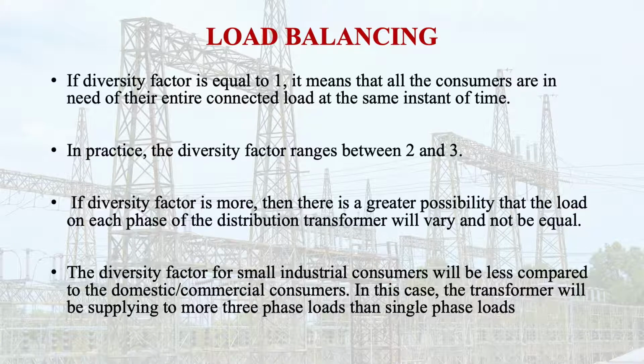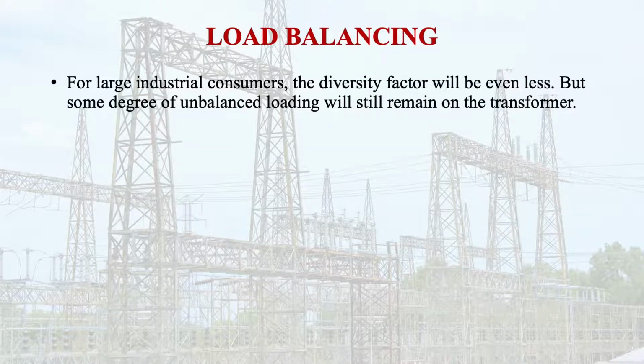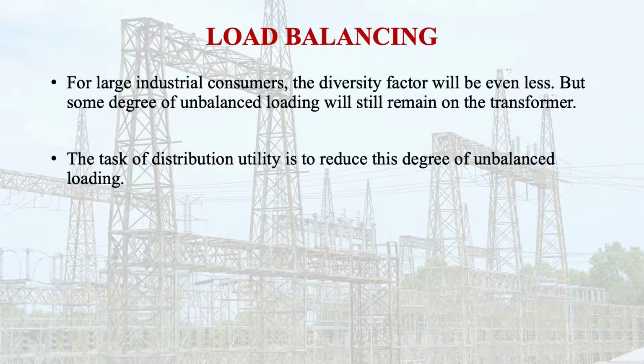Now consider the electric utility which is supplying power to small industrial consumers. In this case, the transformer will be supplying more 3-phase loads than single-phase loads. So the diversity factor for small industrial consumers will be less as compared to domestic or commercial consumers. For the large industrial consumer, the diversity factor will be even less. But some degree of unbalanced loading will still remain on the transformer. So the task of the distribution utility is to reduce the degree of unbalanced loading.